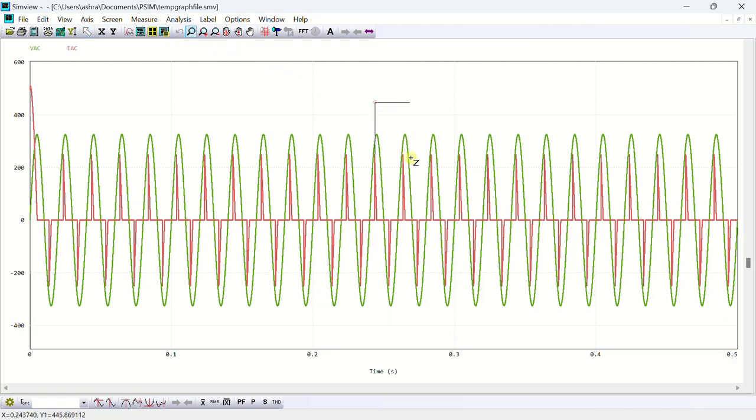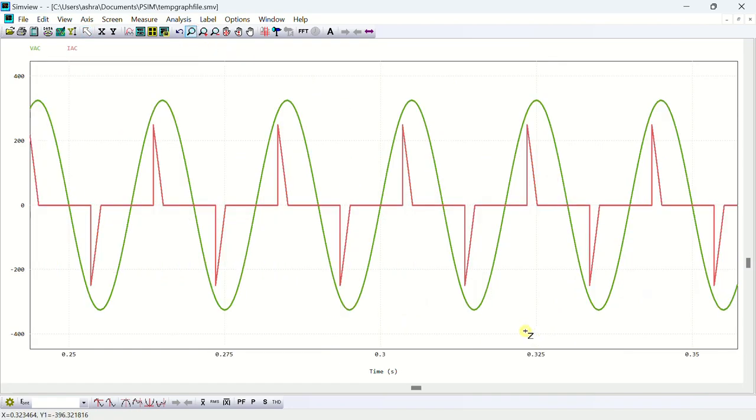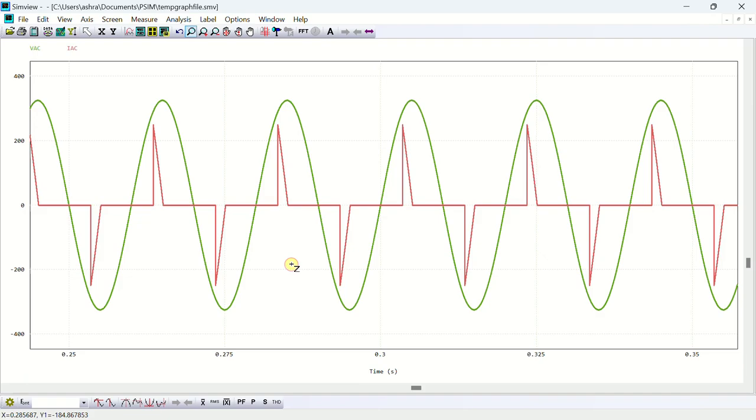This is the input voltage and current, and as you clearly see that, the current is not sinusoidal and it contains lots of harmonics. And if the equipment draws this kind of current from the utility grid, it can create lots of power quality issues. So this is one reason why diode bridge rectifier is normally not used in power supplies of power rating more than 75 watts.